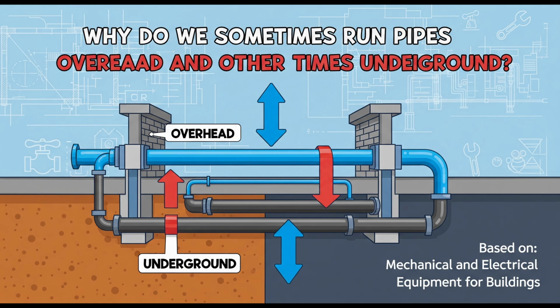Right, let's kick things off with electrical systems. That seems like a common place where you first hit this overhead versus underground thing right at the edge of the property. So when a building needs power, what are the basic ways it gets there? Well, for electrical service, the main choice is between what's called overhead service and underground service. Overhead is probably what most people picture: those power lines on poles running above ground, connecting directly to the building's main electrical panel. It's often simpler, maybe more direct in some situations, kind of the default in many older residential areas.